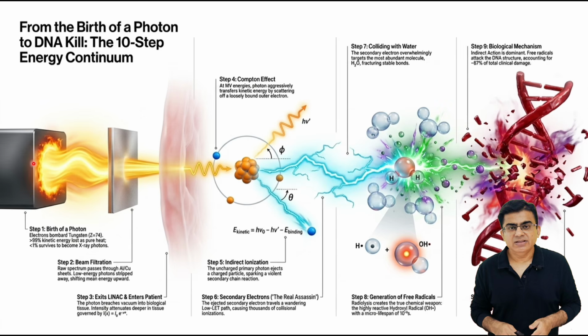Step 1 begins with the birth of a photon. Here, in this step, high-speed electrons bombard a heavy tungsten target. More than 99% of the kinetic energy is waste and lost as pure heat. Only approximately 1% survives to become actual X-ray photons.